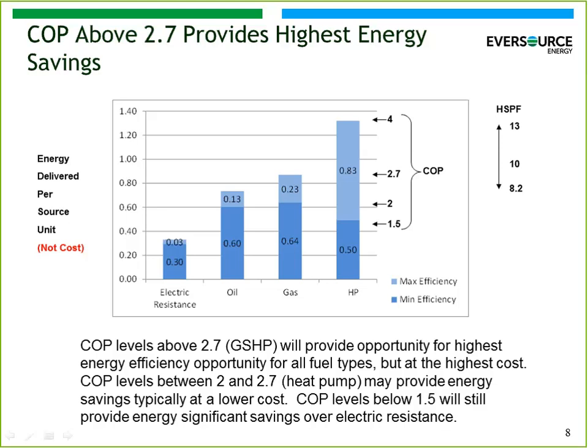If you look at electric resistance, the number we're coming up with is about 0.33. You say to yourself, why is that at 0.33? The reason is because power plants have to use energy to generate electricity — they're certainly not 100% efficient. Granted, some of our generation is renewable, but a lot of it isn't, so this is kind of like a weighted average of our generation fleet in New England. In addition, there are line losses. So when all is said and done, it takes about one unit of energy at the power plant to generate about a third of a unit of energy for the end-use consumer.